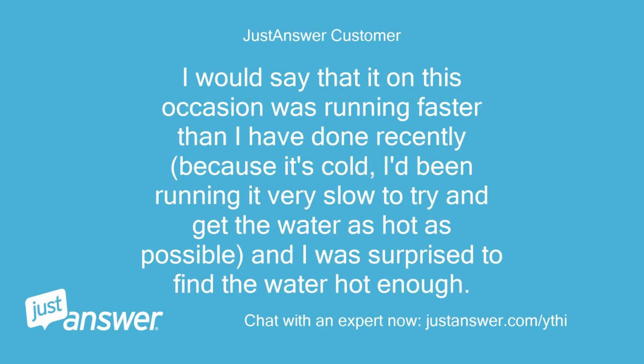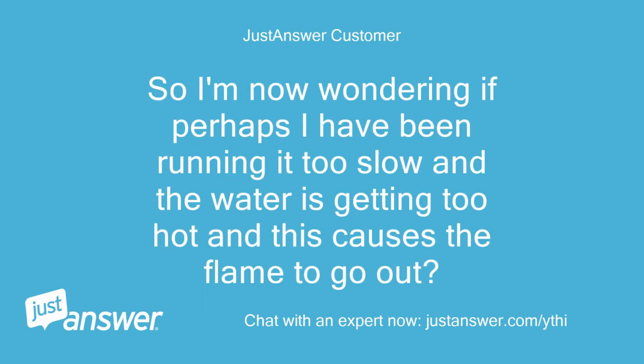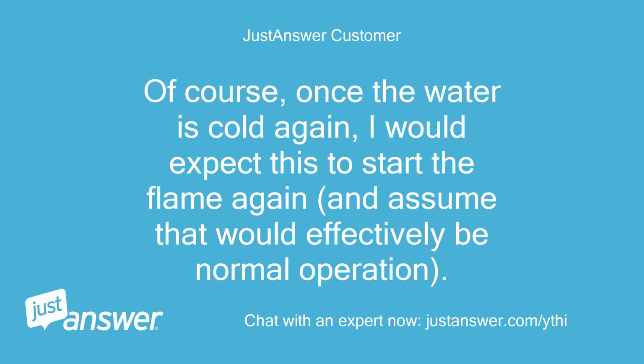I would say that on this occasion it was running faster than I have done recently, because it's cold. I've been running it very slow to try and get the water as hot as possible, and I was surprised to find the water hot enough. So I'm now wondering if perhaps I have been running it too slow and the water is getting too hot and this causes the flame to go out? Of course, once the water is cold again, I would expect this to start the flame again, and assume that would effectively be normal operation.